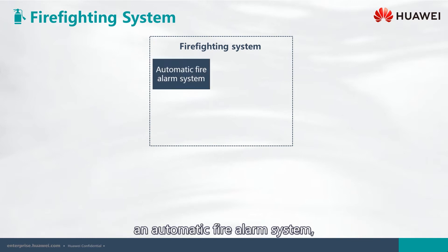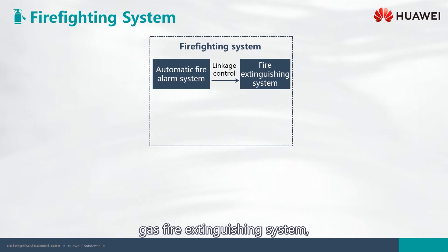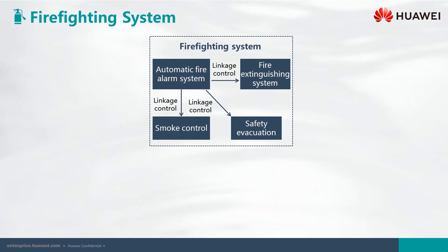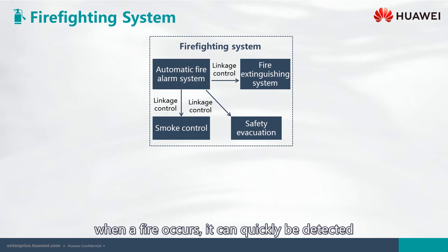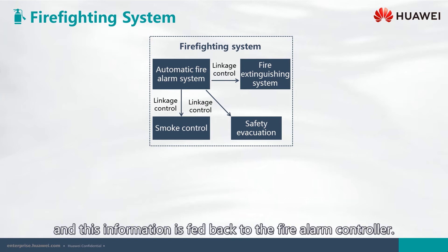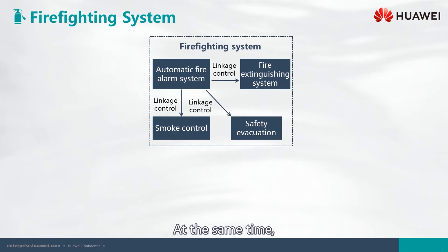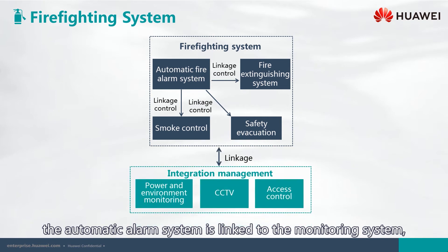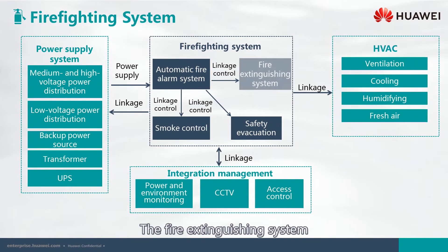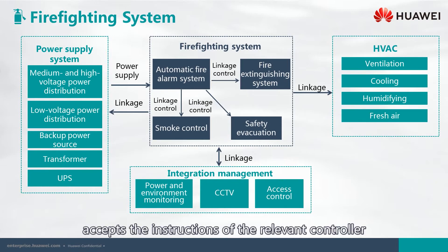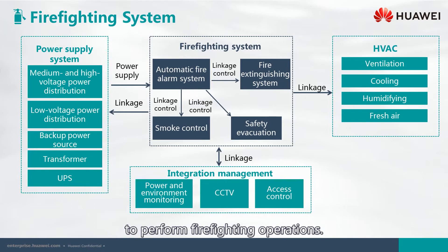The firefighting system is made up of four subsystems: an automatic fire alarm system, gas fire extinguishing system, smoke control system, and safety evacuation system. When a fire occurs, it can quickly be detected and this information is fed back to the fire alarm controller. At the same time, the automatic alarm system is linked to the monitoring system, the power supply system, and the HVAC system. The fire extinguishing system accepts the instructions of the relevant controller and controls the firefighting equipment to perform firefighting operations.